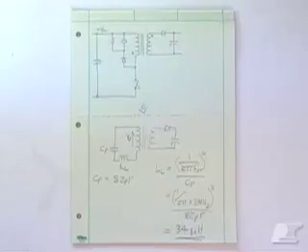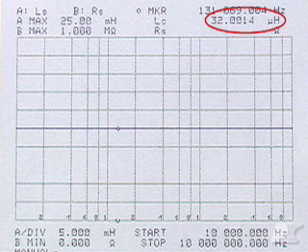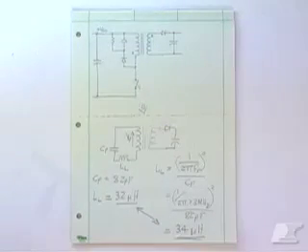As before, I've pre-measured this transformer, and the value I got from our impedance analyzer was 32 microhenries. So we can see here that this is actually a very, very close estimate and a very useful way of estimating the value of the leakage inductance.